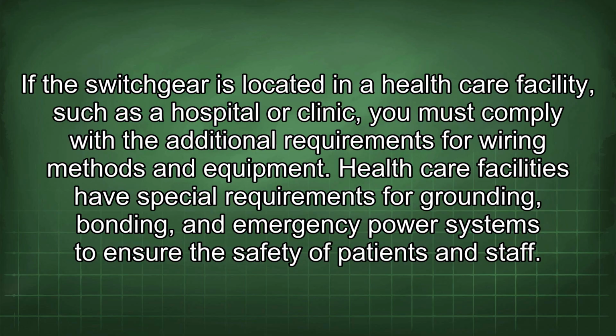Consider the requirements for healthcare facilities, as specified in Article 517. If the switchgear is located in a healthcare facility, such as a hospital or clinic, you must comply with the additional requirements for wiring methods and equipment. Healthcare facilities have special requirements for grounding, bonding, and emergency power systems to ensure the safety of patients and staff.